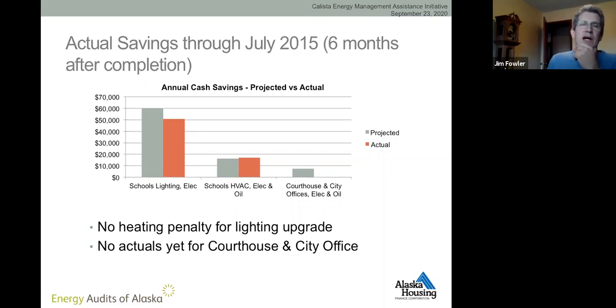The reason that the lighting savings came in a little bit low is because the lighting contractor did not consider what's called a heating penalty. When you reduce the amount of wattage produced by lighting in a building, you increase the need for heat during the heating season. So then let's go to the next slide.